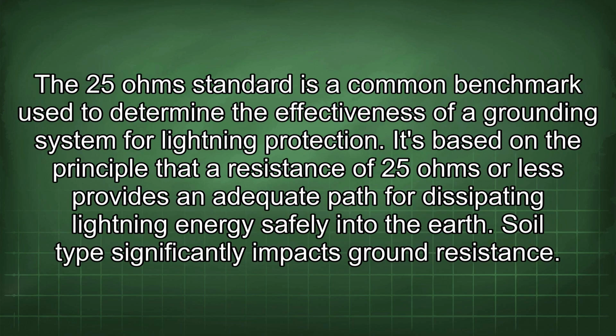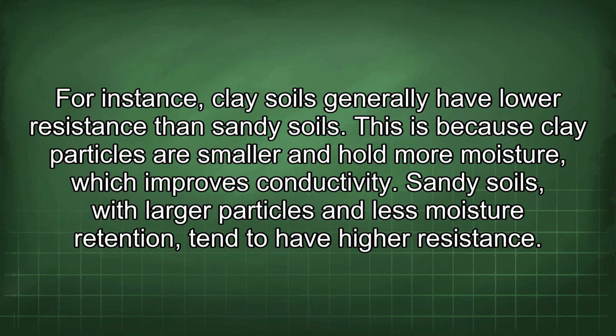The 25 ohm standard is a common benchmark used to determine the effectiveness of a grounding system for lightning protection. It's based on the principle that a resistance of 25 ohms or less provides an adequate path for dissipating lightning energy safely into the earth. Soil type significantly impacts ground resistance. For instance, clay soils generally have lower resistance than sandy soils. This is because clay particles are smaller and hold more moisture, which improves conductivity. Sandy soils, with larger particles and less moisture retention, tend to have higher resistance.